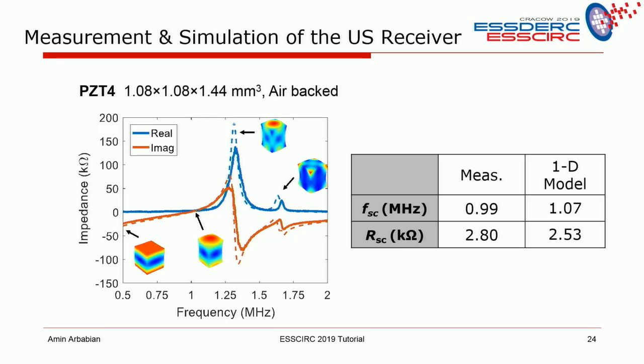I'm going to talk a little bit about this, but the operation is usually between the short-circuit resonance and open-circuit resonance. And then you have different modes. In short-circuit and open-circuit resonance, you have your longitude, length-expander modes, and depending on the disk mode, depending on the aspect ratios. But you also have higher order modes that kick in, starting at, for this particular piezo, about 1.6, 1.7 megahertz.